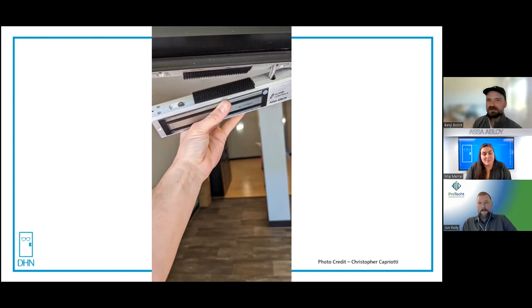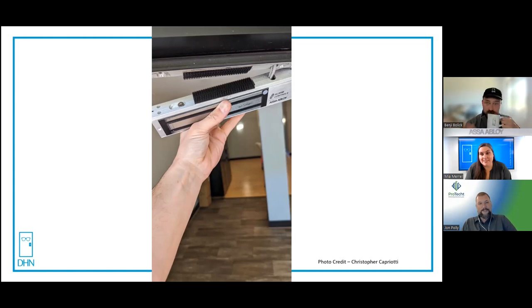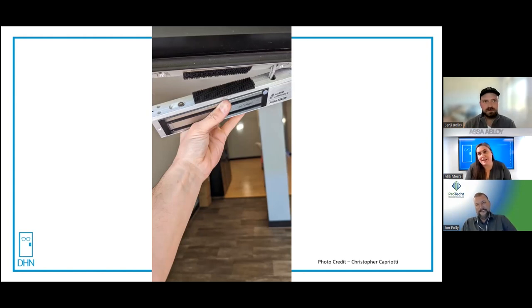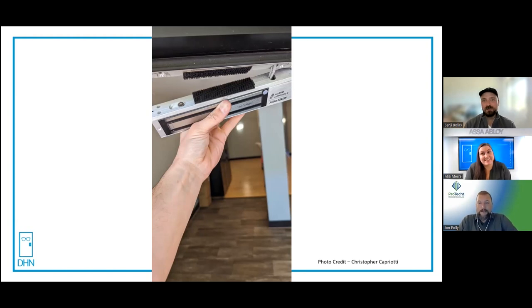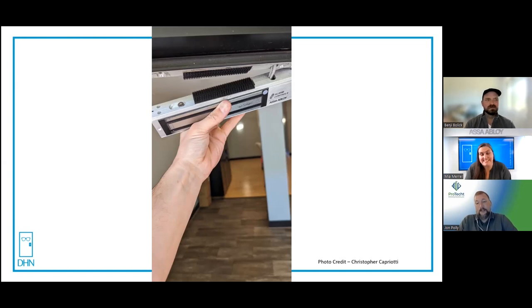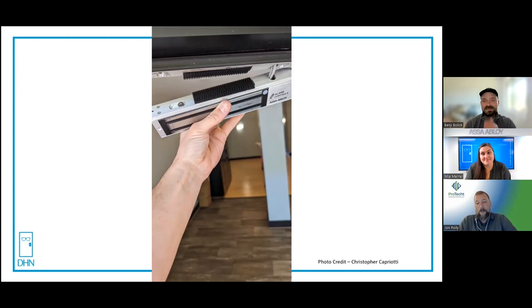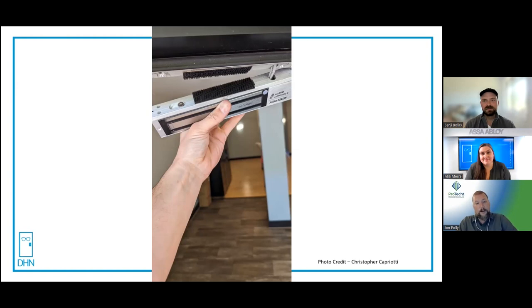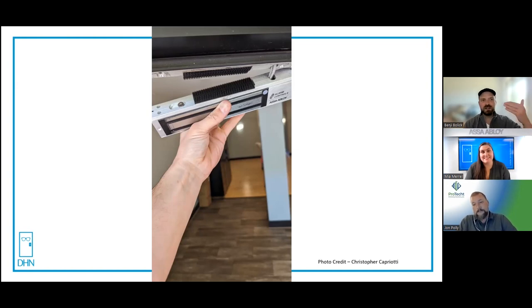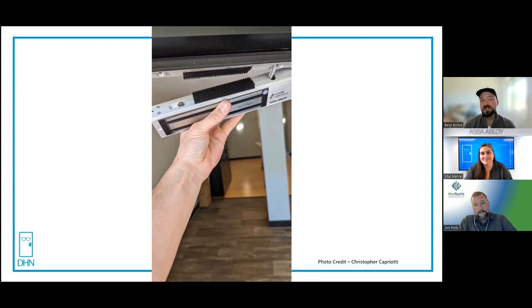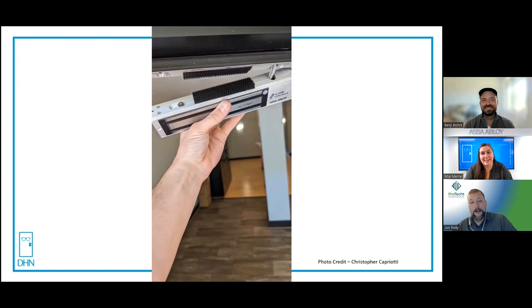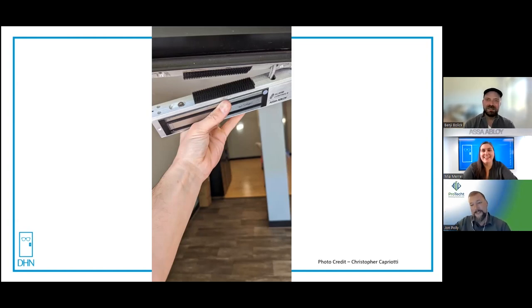I feel like if we had more information we could easily give this a 10, but from a liability standpoint, life safety, yeah, it's high. I would say eight. Guys, I'm sort of close to a 10 because your building isn't secure. Unless they have another lock, you have no building security and you've created a liability that is going to injure or already has injured somebody. You pull hard enough on that door and those wires are just gonna rip out. That armature plate, that lock is coming off. It does appear like it's an exterior door—you can see the weather stripping there. I didn't think about it from a security standpoint. This is really bad.